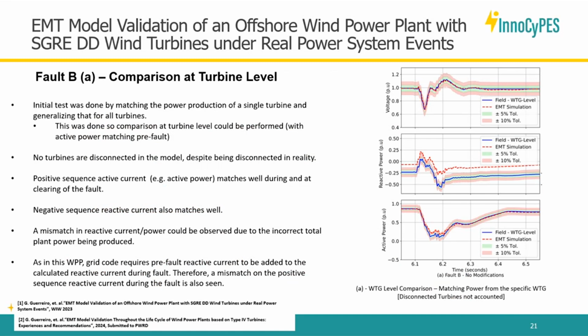Going one by one: first, what if we assume the whole plant is producing the power of a specific wind turbine? In this case, it was a turbine producing around 90%. This is not a good assumption, because the plant as a whole was not producing that, but we wanted to see what happens. There is a large mismatch, because we forced the model to behave as if it were producing that power. At the turbine level, active power matches relatively well, and voltage too, but reactive power is completely off, because the plant was not actually producing that power collectively. When we force that to happen, the plant requires more reactive power injection to keep the same voltage.